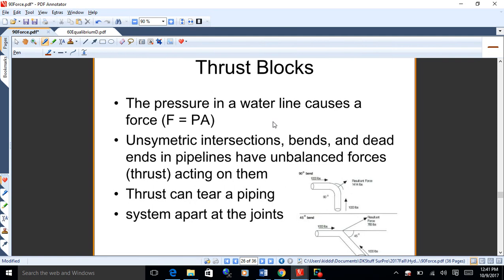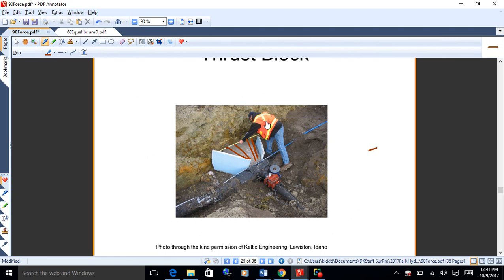Now there's other ways to accomplish this too. There's fancy mechanical joints. You all know about the joints in water lines. Most of them, garden variety, are push on, just bell and spigot kind of thing, push them on. The pipes are so big and heavy and you've got the backfill around them, it holds them together. If you get into special situations, the extreme step is a flange to flange connection, but that's strong. It's very strong, but it's rigid and it's unwieldy.